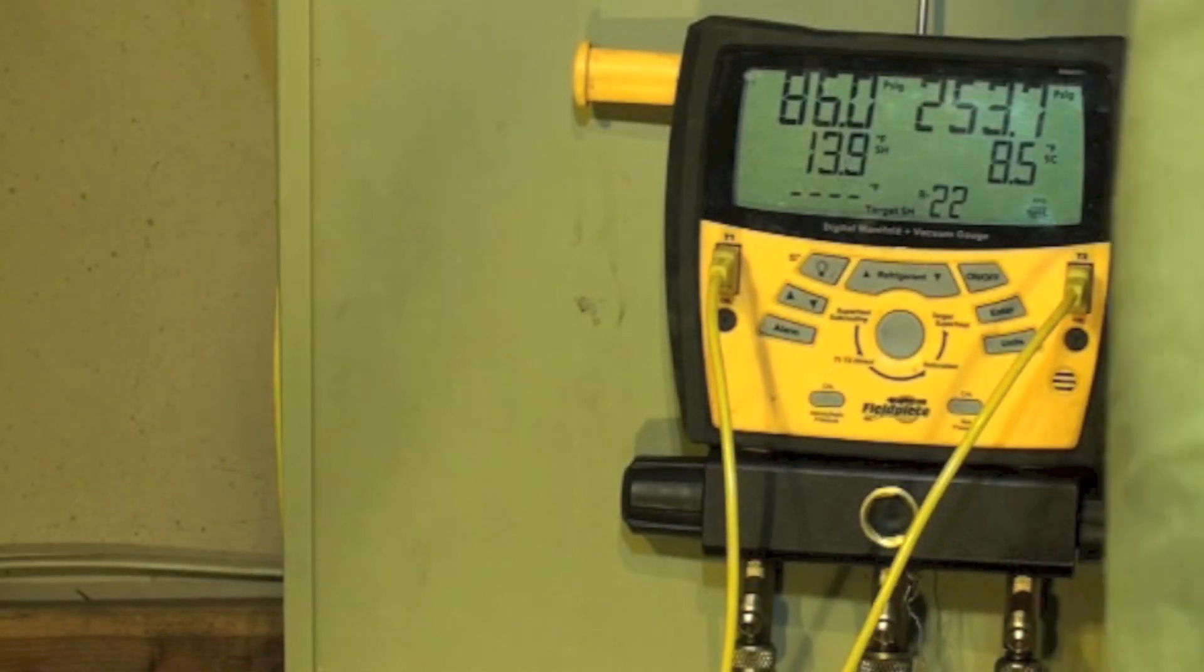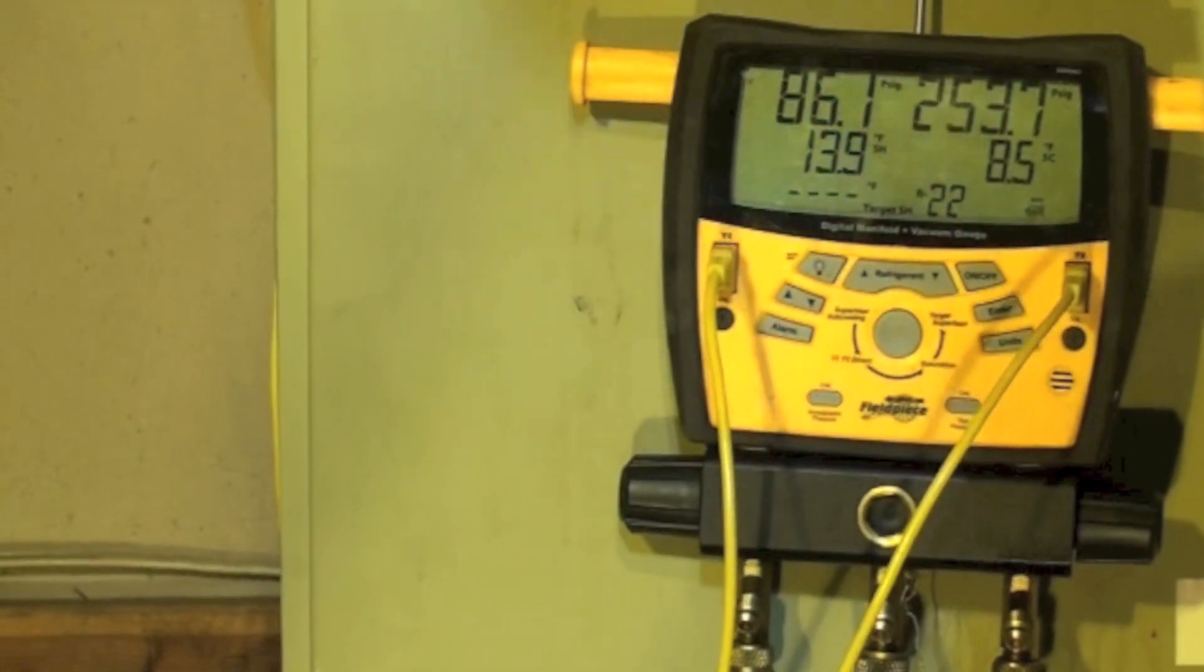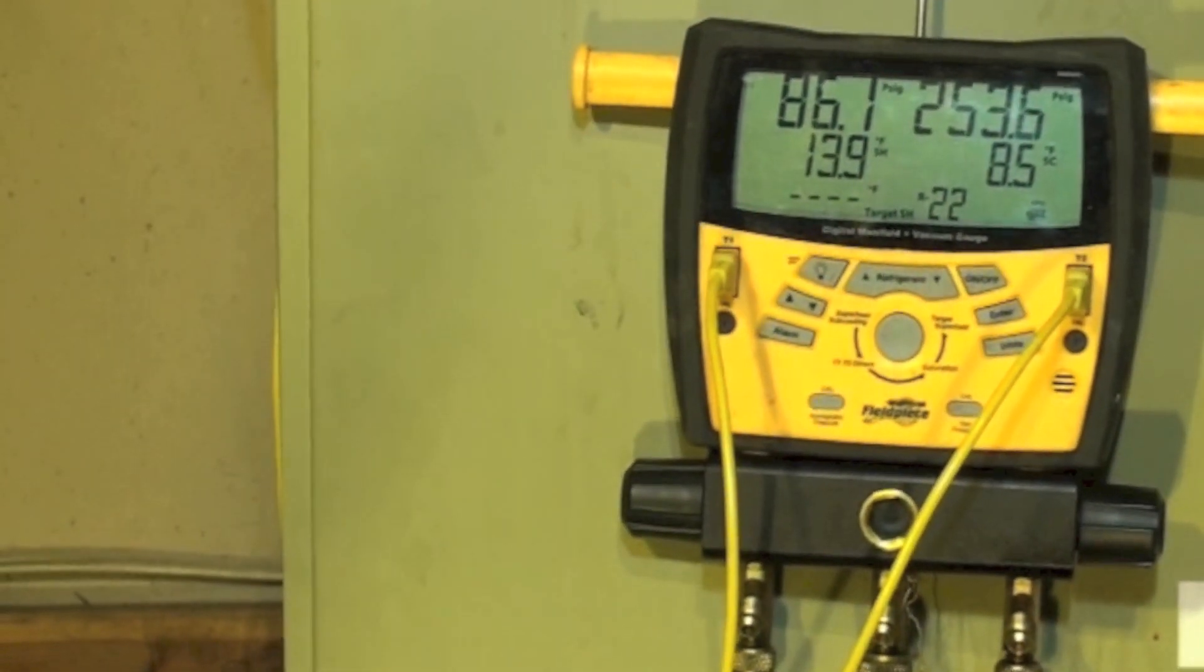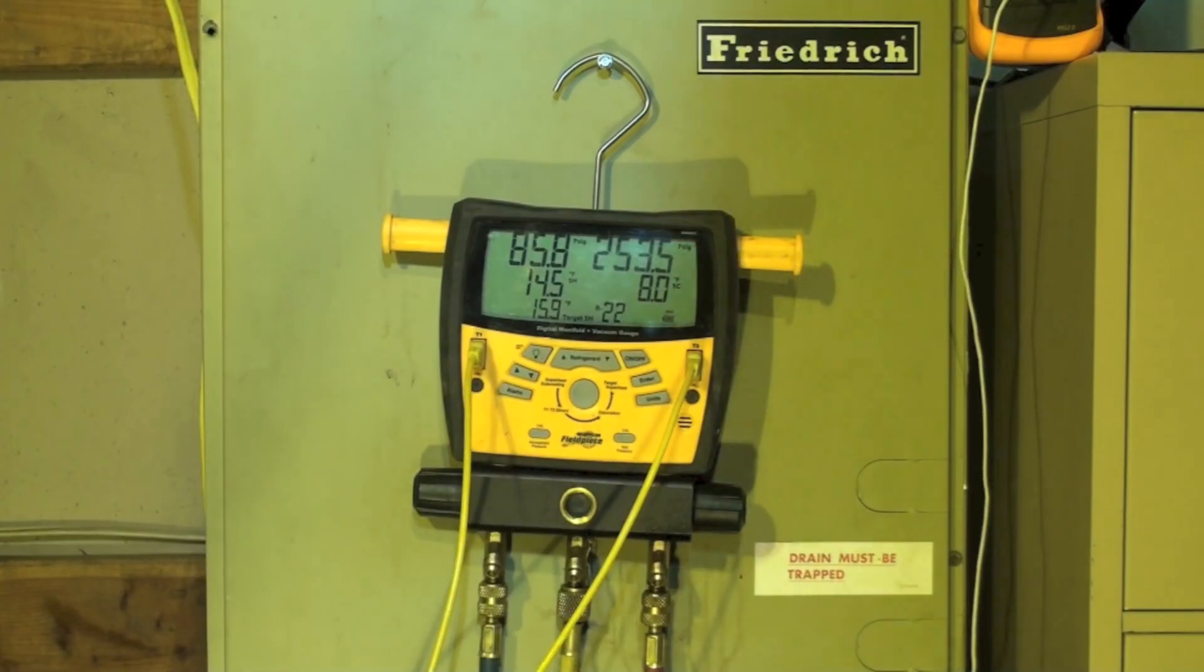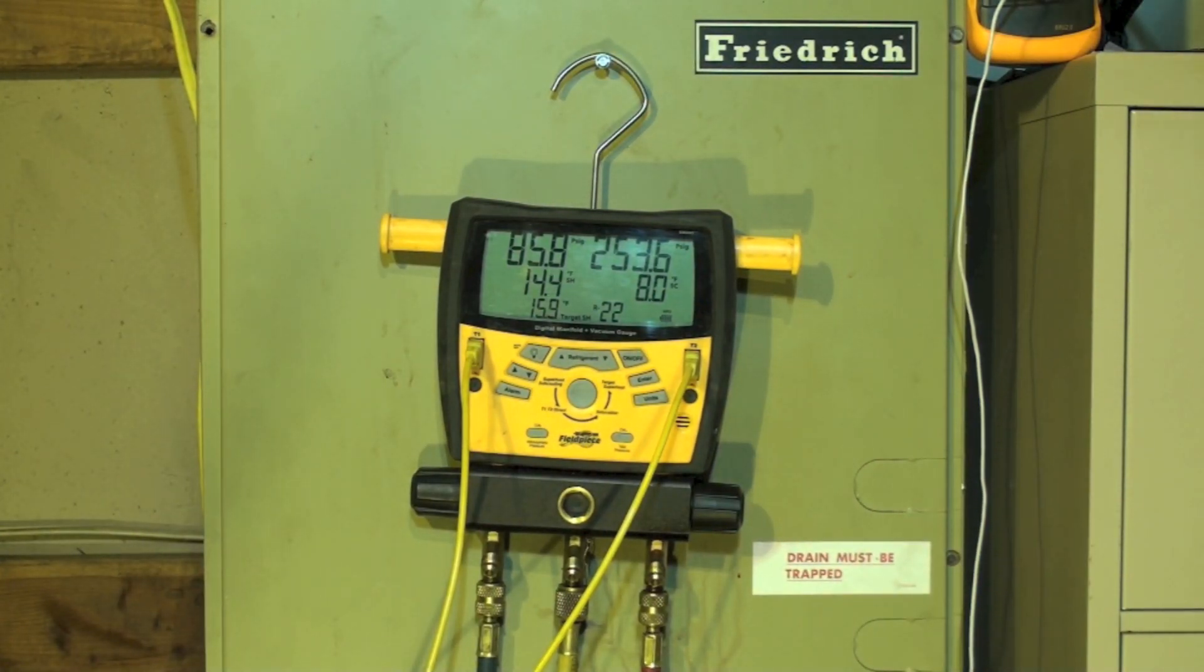Let me go ahead and do that target superheat again, and we'll see if it's changed. Okay, I've recalculated the target superheat. I'm at 14.4 and it's 15.9.